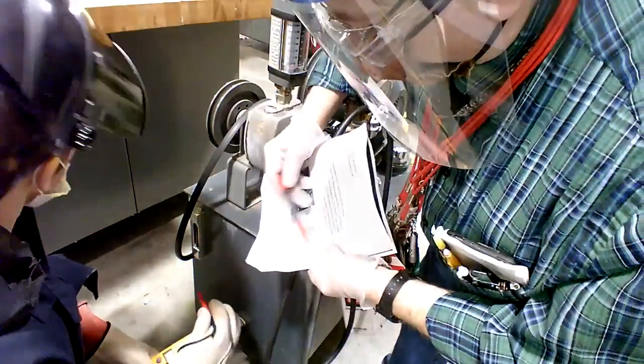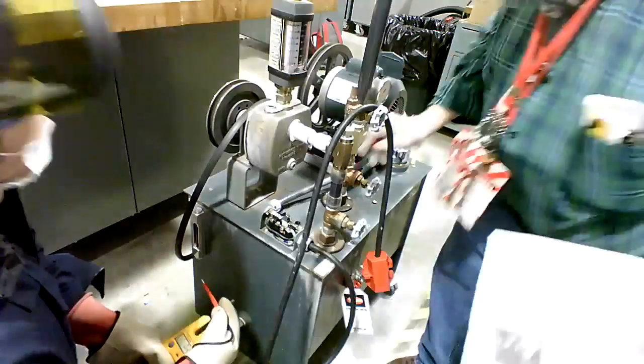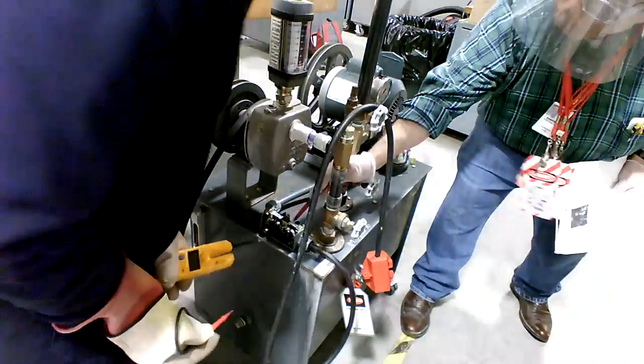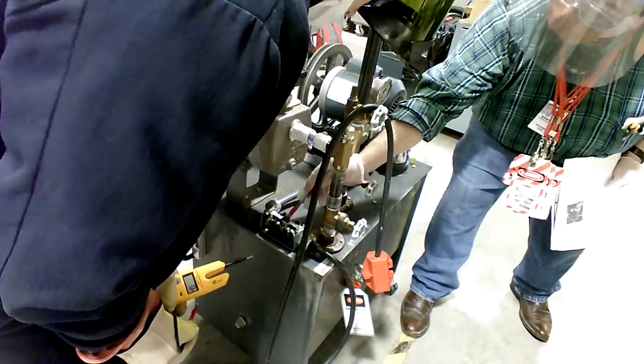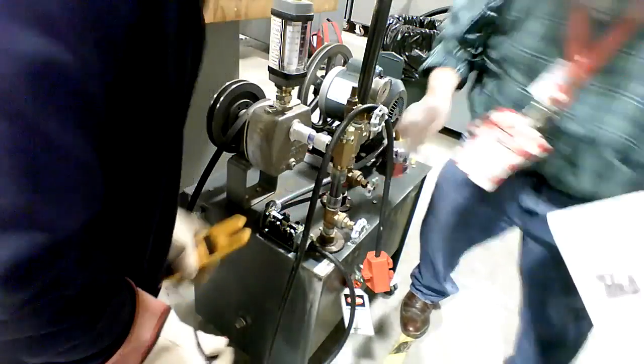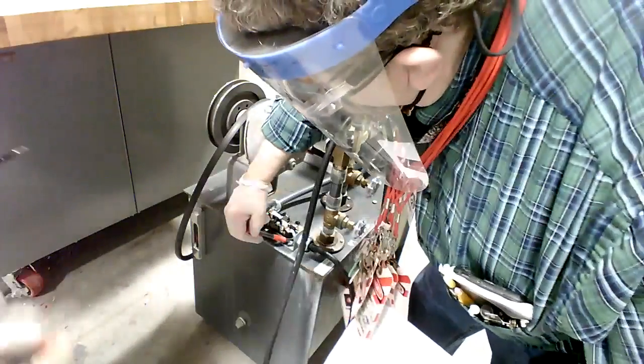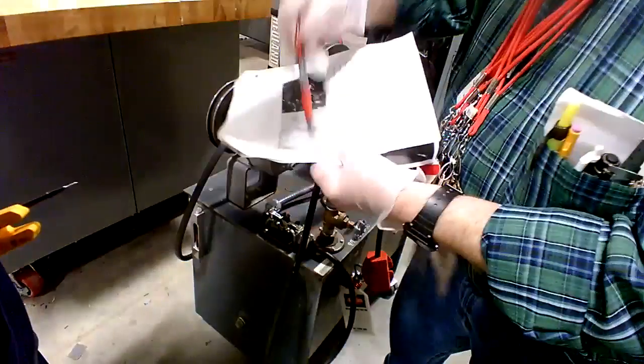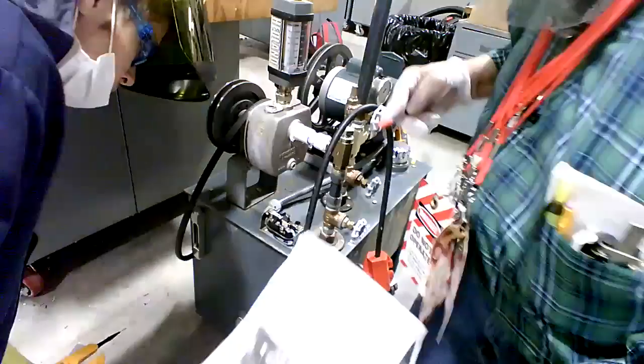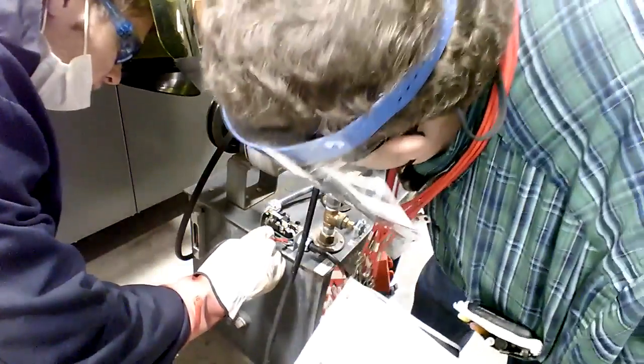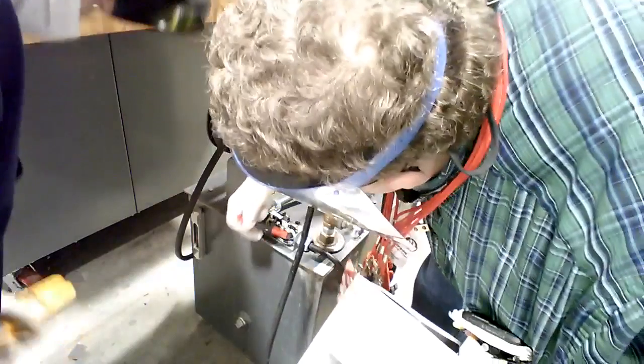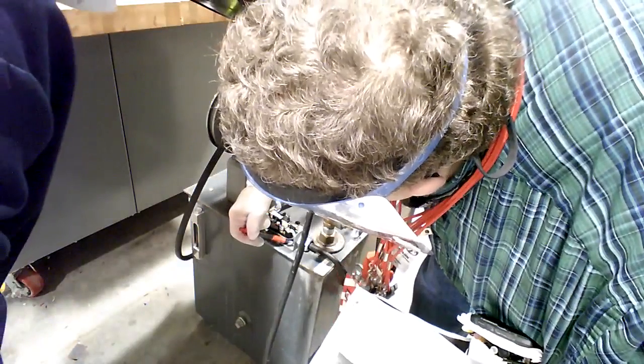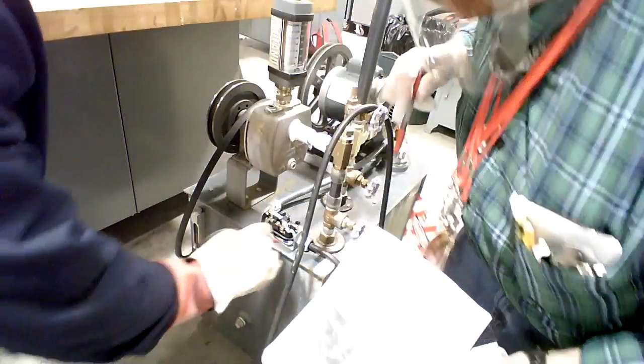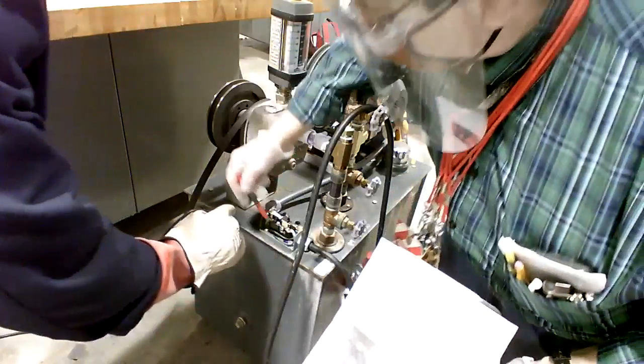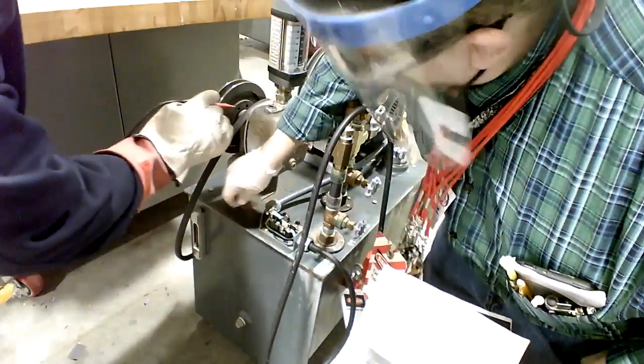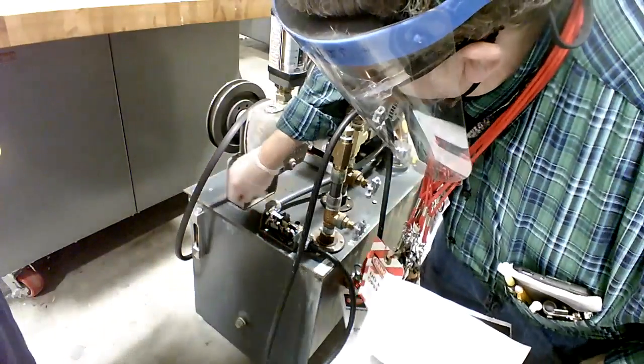The neutral, it goes straight to the motor. So look behind here, you see a white wire behind this. And both of the incoming and the outgoing white wires are lined up. They're continuous. The ground wires, both of them meet on that screw. And so the ground is continuous, okay? Yeah, there's two green wires under that screw there. Is that the black from? Is that how you get power to this? To the motor, yes. Yeah, that black one leaves and it goes out to the motor.